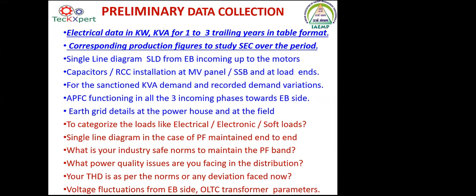Then comes the capacitors, what all has been installed, because the old school was, for the given kVA, let us say 40% rated of capacitors in all the industries. That is not so now. The concept has totally changed, because the industry has both electrical loads and electronic loads, linear loads and non-linear loads, where especially the branded VFDs already maintain around 0.9 to 0.95 as the power factor. In that case, too much of capacitors in the powerhouse is going to be a loss to the industry. So for the sanctioned demand and the recorded demand variations studied for a year, we know where we stand.